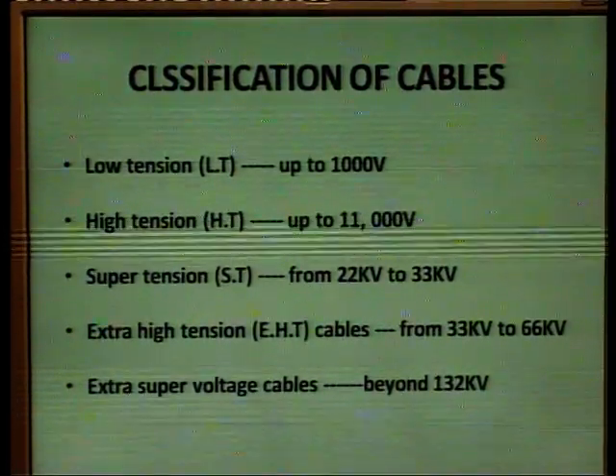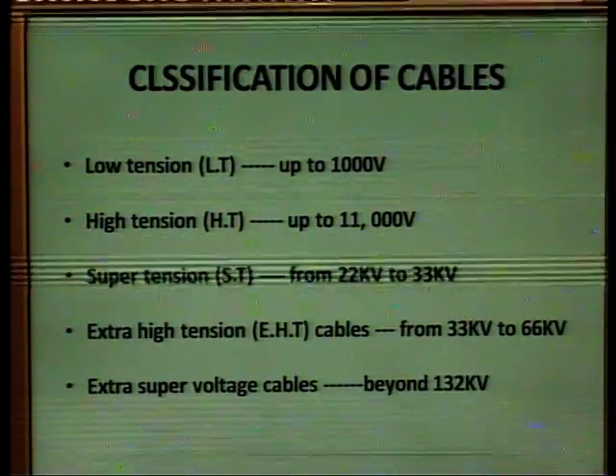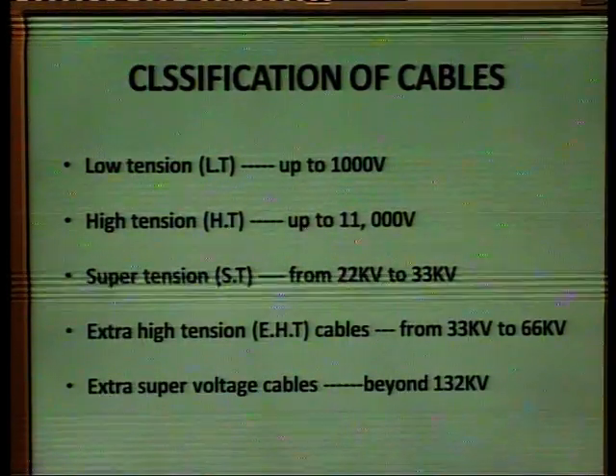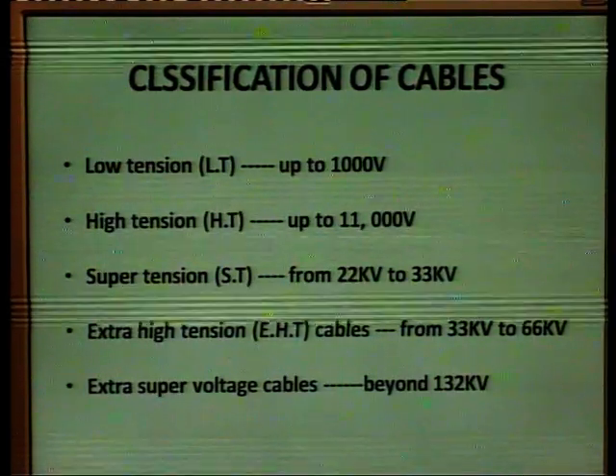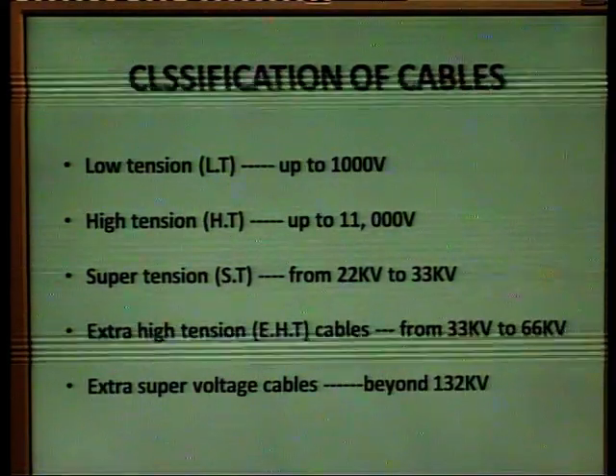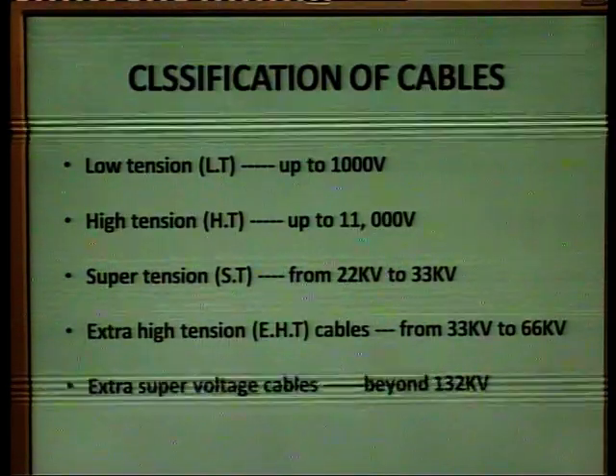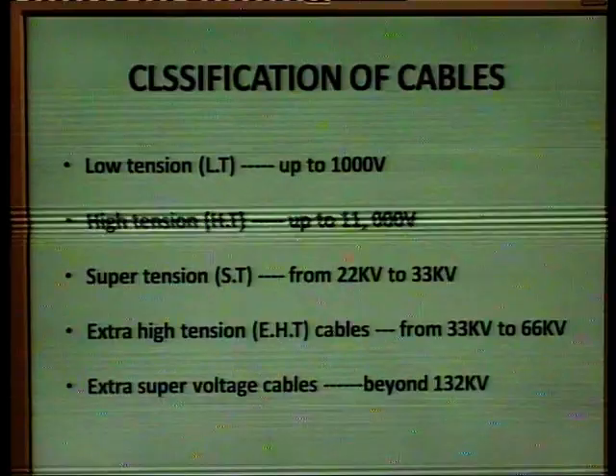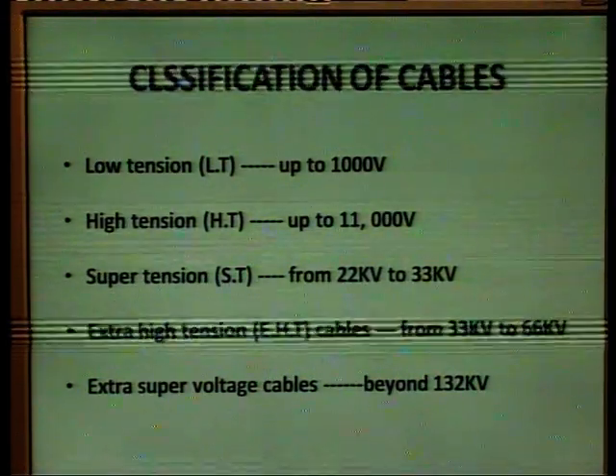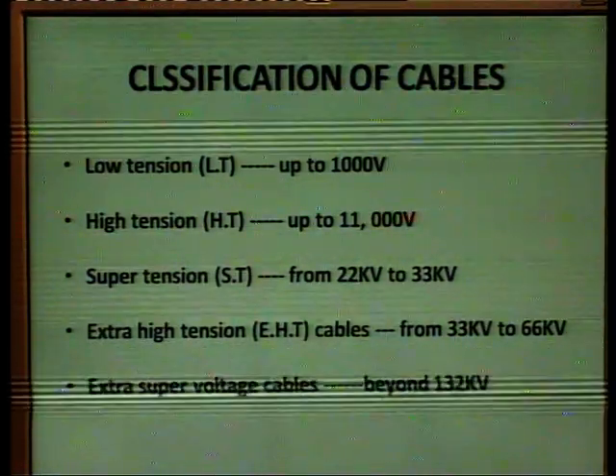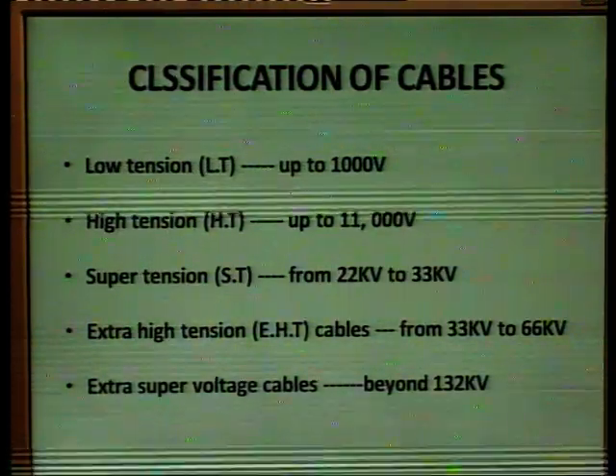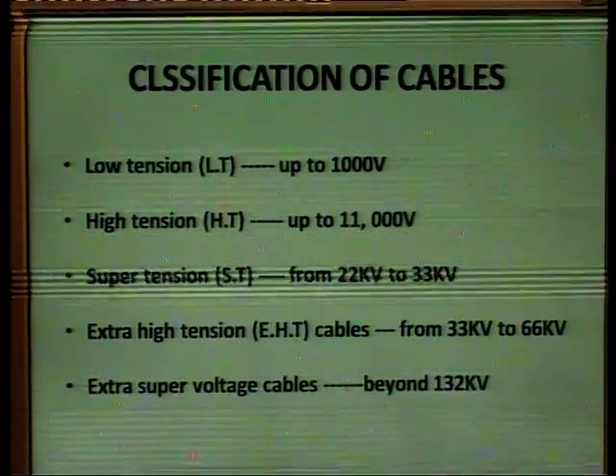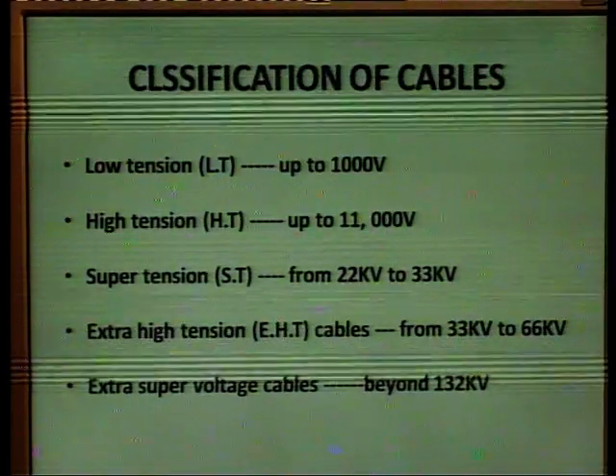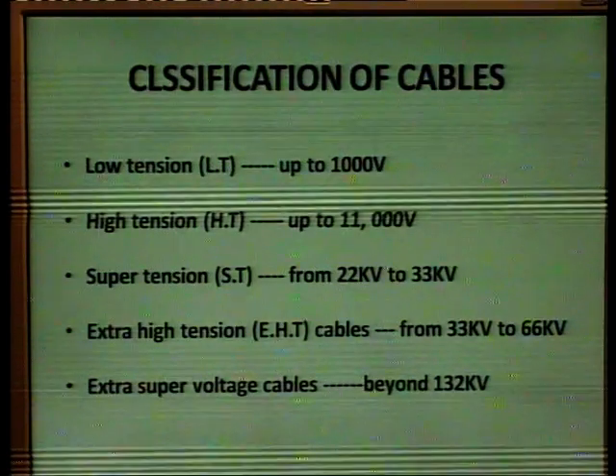Then we have the classification of the cables. First is the low tension or LT cables. These are used up to voltages of 1000 volts. Then we have the high tension cables, known as HT cables, and they are used up to 11,000 volts. Then the super tension ST cables, and these range from 22 kV to 33 kV. Then the extra high tension EHT cables, which range from 33 kV to 66 kV. Then extra super voltage ESV cables. They are used beyond 132 kV.